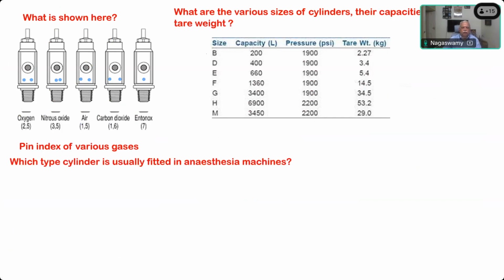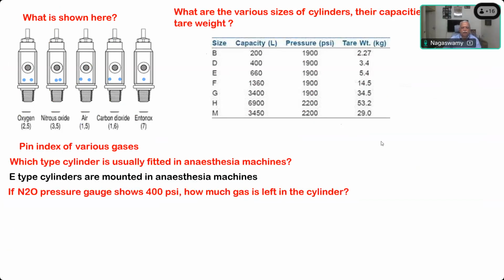Which type of cylinder is usually fitted in anesthesia machines? E-type cylinders, sir. E-type, very good. So it is the E-type cylinders that are mounted in the anesthesia machine. If the nitrous oxide pressure gauge shows 400 psi, how much gas is left in the cylinder? What will be the pressure in a full nitrous oxide cylinder when you start the case? Supposing you fit a full cylinder and open the valve, it will show 750 psi.